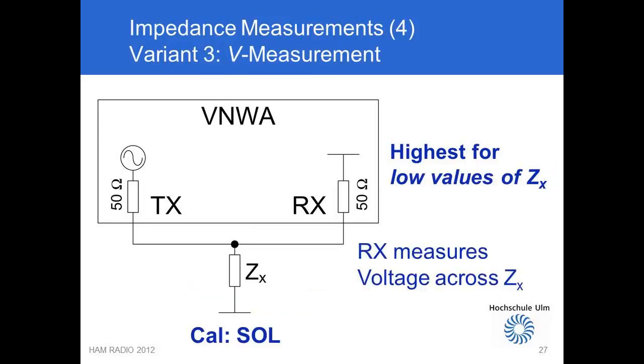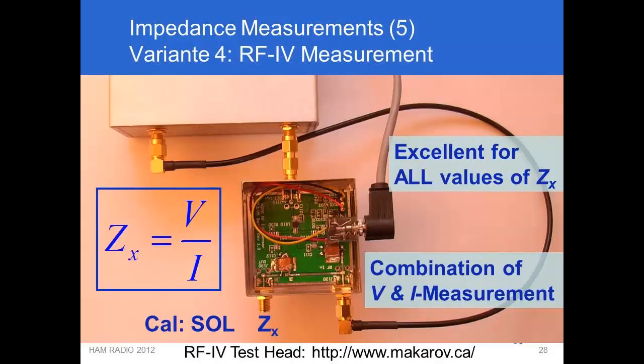A third method is to measure voltage drop across the unknown impedance, where the RX port is measuring voltage and the TX port is used as current source, although not ideal. This setup works perfectly for low impedances close to short circuit, but for very high impedances the voltage does not change very much. The fourth method is to combine the two previous methods by measuring RF-IV, meaning RF current and RF voltage independently, followed by calculations of the quotients. Measurements of all impedances can be performed, both high and low impedances.